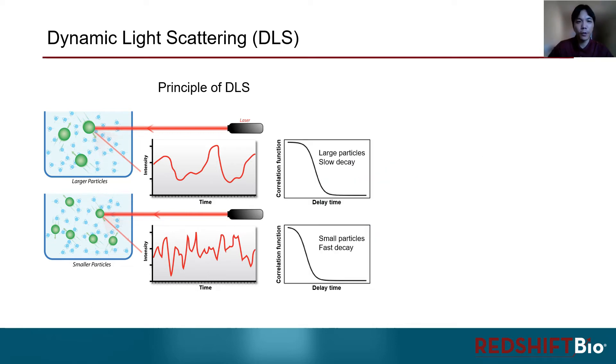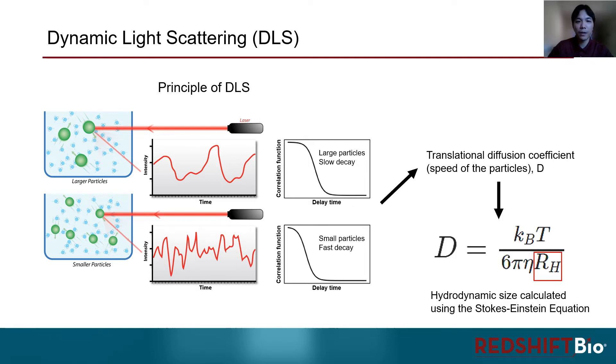For larger particles that diffuse slower, the correlation signal loss will take longer. For smaller particles that diffuse faster, the correlation signal will decay faster. And as we can see here, this process is plotted as a correlation function. This is then used to calculate the translational diffusion coefficient, or simply the speed of the particles. From here, the hydrodynamic size of the particles is calculated using Stokes-Einstein equation.